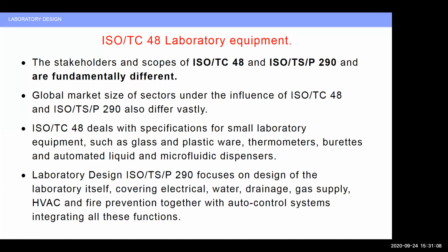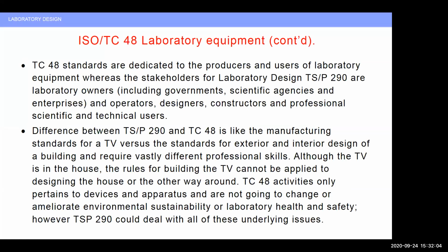Now, concerning the link with ISO TC 48 on laboratory equipment, we can see that the stakeholders, scope and global market size for ISO TC 48 and the new technical committee are fundamentally different. ISO TC 48 deals with specifications for small laboratory equipment, such as glass, plasticware, thermometers, burettes, and automated liquid and microfluidic dispensers. Whereas the laboratory design committee will focus on the design of the laboratory itself, covering electrical, water, drainage, heating and ventilation and air conditioning, fire prevention, together with the control system, integrating all these functions. So we can see that these are very different subjects.